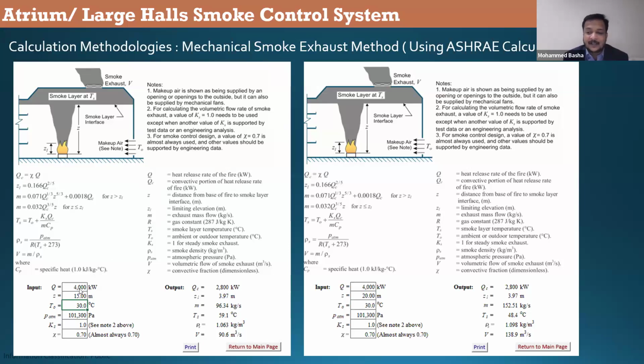Q. This is where we don't have sufficient information at certain times. Sometimes we have the information. So I have mentioned Q here as 4,000 kilowatt. Where is the 4,000 kilowatt taken from? It depends on the burning material, basically. What material is burning at that place? In the Qatar Civil Defense requirement, they are giving us a guideline only for car parks. So you need to assume in a sprinkler-controlled car park, 4,000 kilowatt is the heat release rate, whereas in non-sprinklered car parks, you need to consider 8,000 kilowatt, which we call 8 megawatts. This is the only guidance we have in the QCDD documents. We do not have any other guidelines.